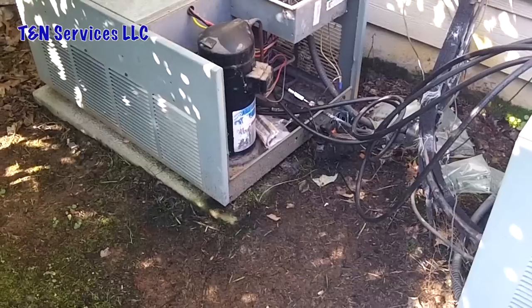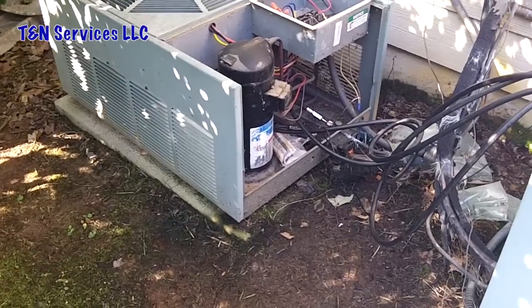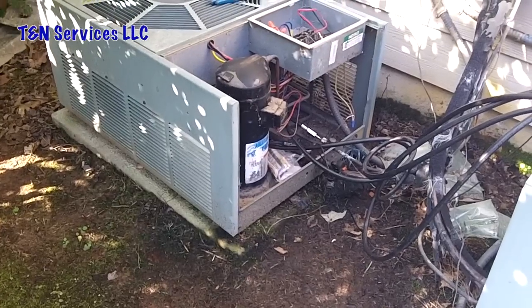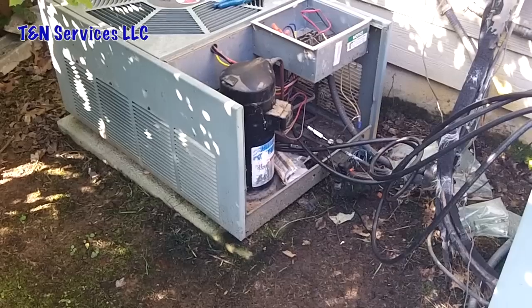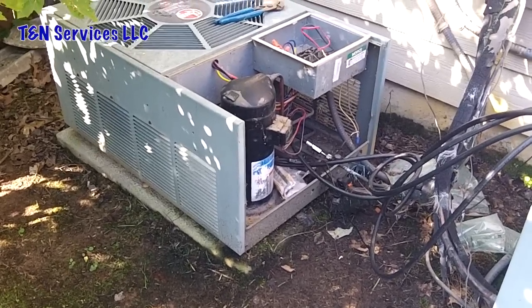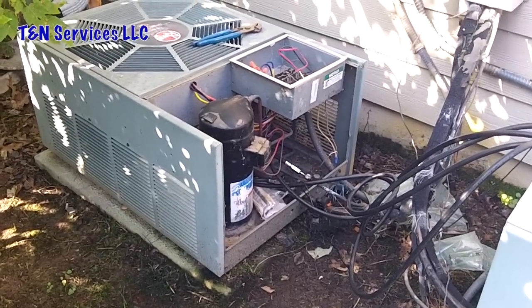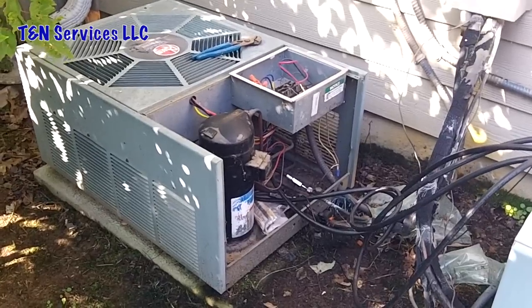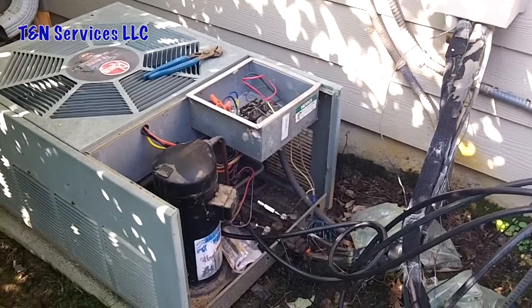Today we're working on a little ton-and-a-half system. Right now it's about 72 degrees out here, but come over in the afternoon and your pressures shoot up to like 88 pounds and back down to 50. High side pressure goes up to about 260-270 and drops down to 170. There are one or two things wrong with it — first I thought it was airflow.